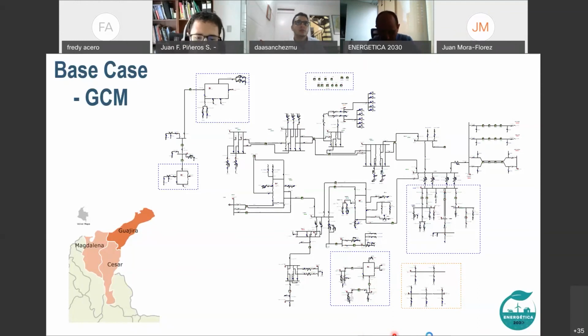I would like to clarify, David, if you accept. I think it's important to say that there are many models. They do not have the features, for example, of the dynamic current support, fault ride through, or even the control strategies. When you put all this together and you have a model that has this behavior, then you have a set of possibilities to test. And my comment was more in the direction that at the end, when you have the final equipment at the place, the best is to have the models of these inverters. Exactly because of that, we don't have models until now. Of course, the manufacturers are really closed with this.